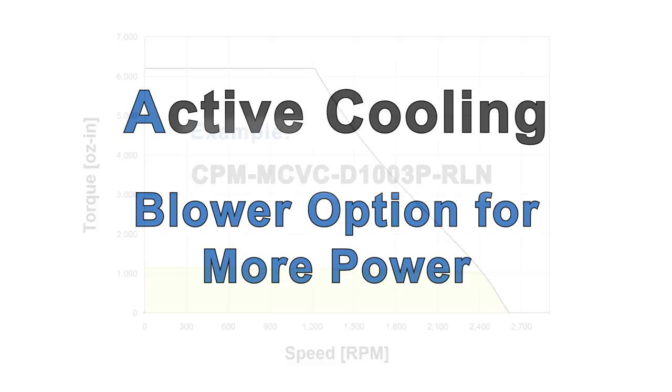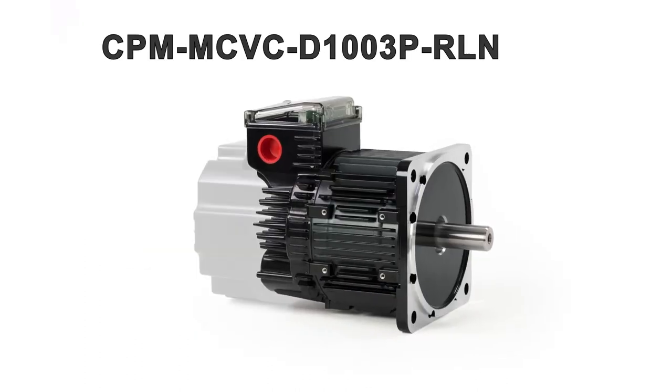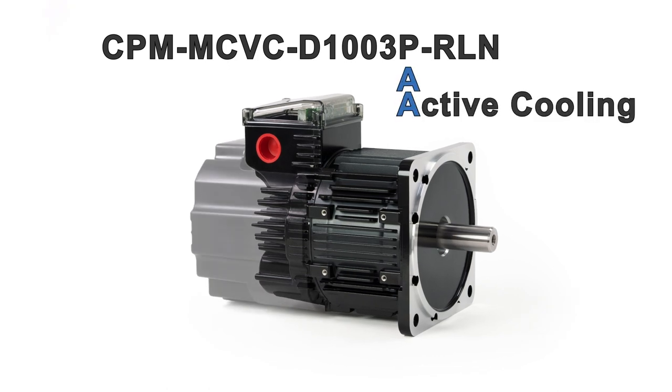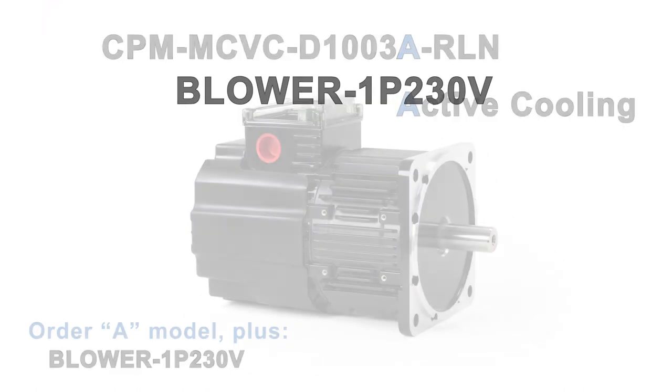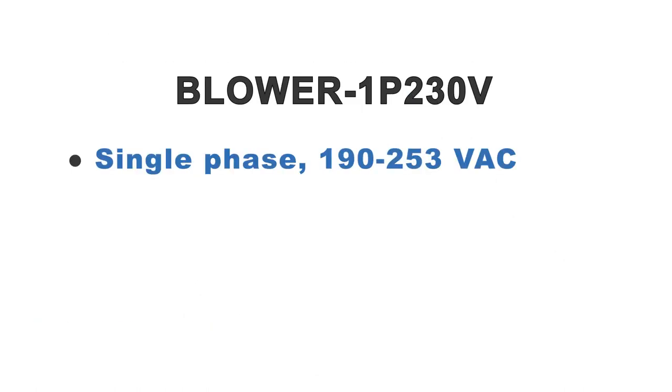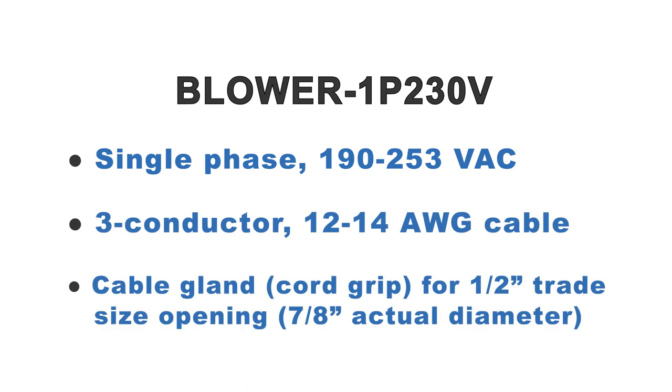Any motor with a 3, 4, or 5 before the P in its part number will gain more than 50% more continuous torque by adding the blower option. To use the blower, you need single-phase 208 volts AC, 3-conductor 12 or 14 gauge cable stock, and a cord grip for a 1/2 inch trade size opening.